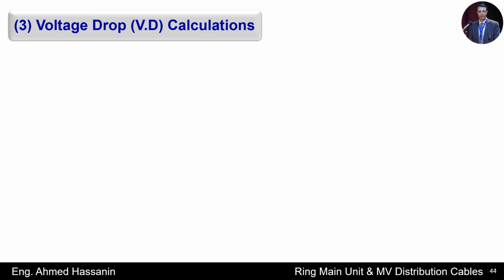In the third section, I will explain how to calculate the individual voltage drop for each part of the medium voltage cables of the ring system and the total voltage drop for the ring system. In the fourth or the last section, I will explain how to know and calculate the short circuit current that the medium voltage cable can withstand at any fault or any short circuit.